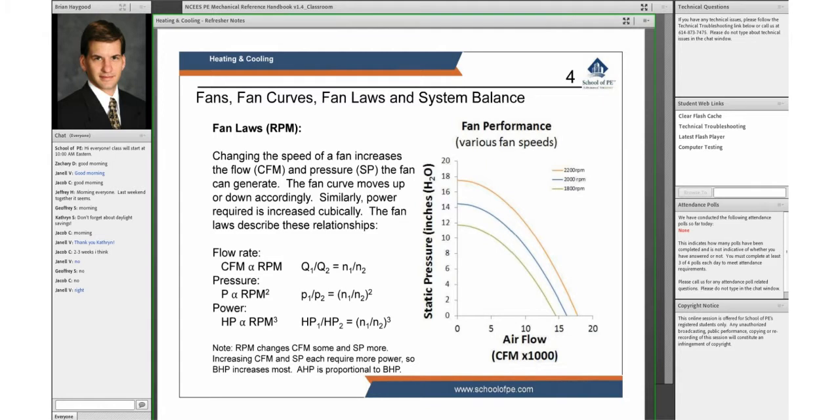The fan performance curve moves up and down as we change speed. Drawn here I've got our original 2,000 RPM curve plus a 2,200 RPM fan curve and an 1,800 RPM fan curve. These would typically appear on successive pages of a book related to this fan, this make and model of fan.